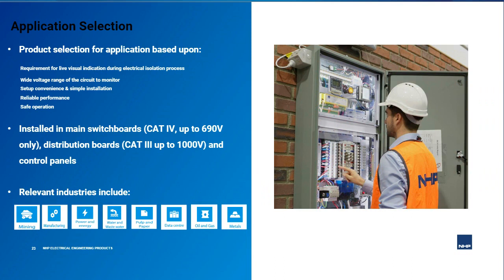We've covered in detail the features and overall function of the REMLIVE unit. Let's now go through some of the selection points that are considered before selecting a liveline indicator. The first point to consider is that the distribution board or control panel facility and application will have a requirement to be serviced over time, which means a technician will come in and electrically isolate the panel and perform a full lockout tagout procedure. The liveline indicator will be useful to this isolation process, and we saw this before, and it protects personnel from shock if the right procedures are adopted.